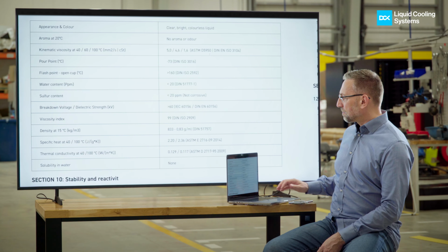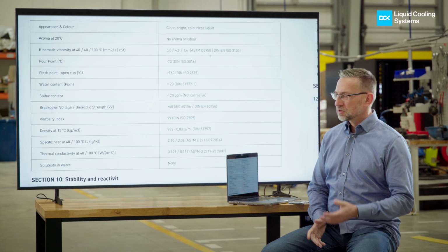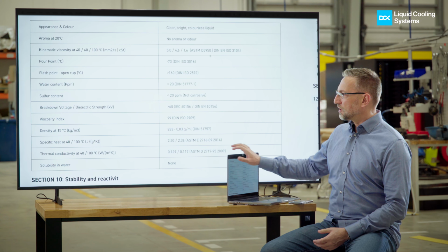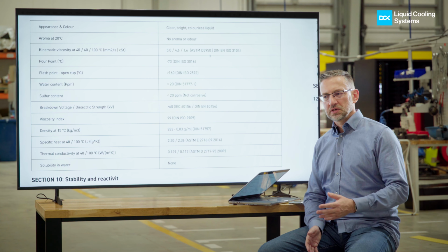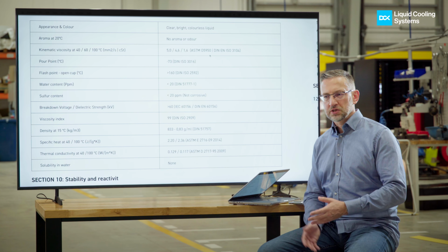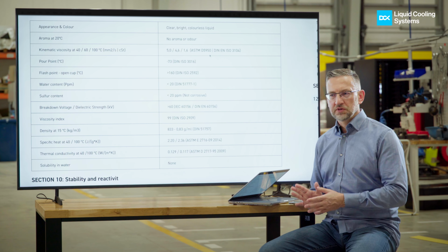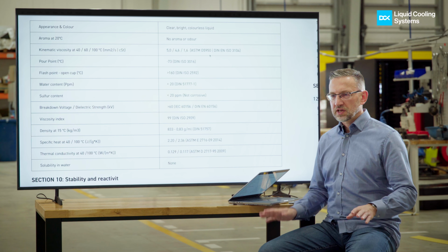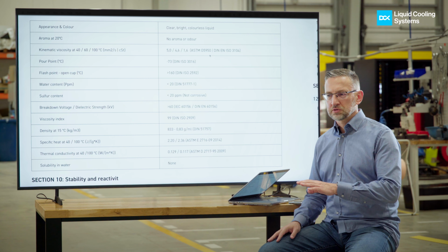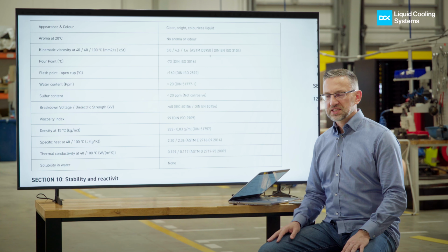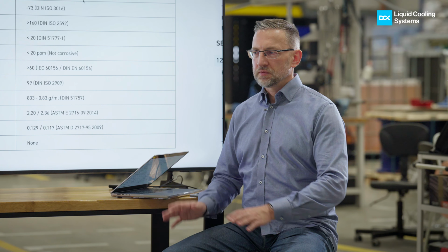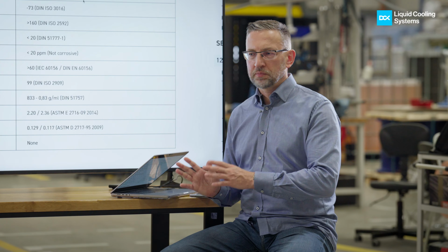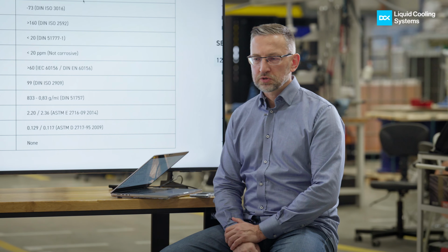We actually try to structure and understand the cooling medium based on its composition, based on whether it's a group 3 or group 4 cooling medium. We use only polyalphaolefin, PAO-based coolants, nothing more. We don't want less capable, less stable coolant like group 3 coolants, GTL coolants. We don't want that. We would like to have PAO-based coolant, and those coolants have different compositions.